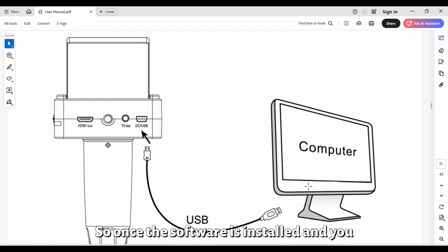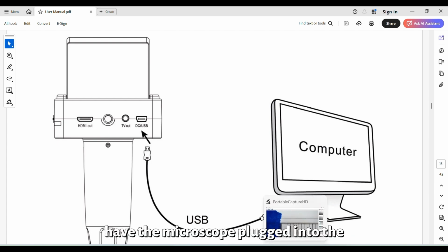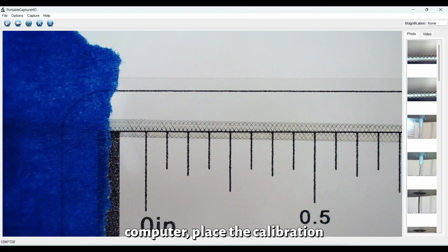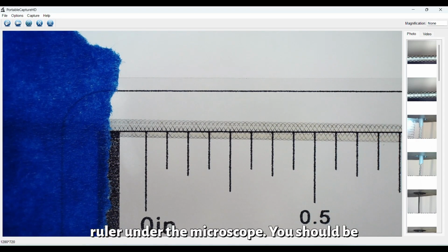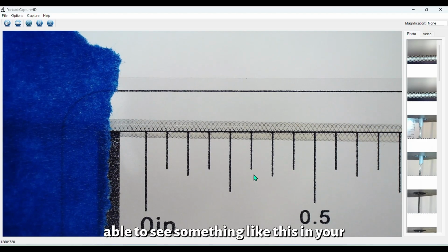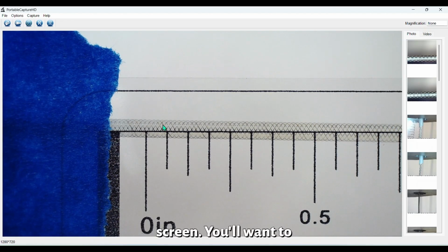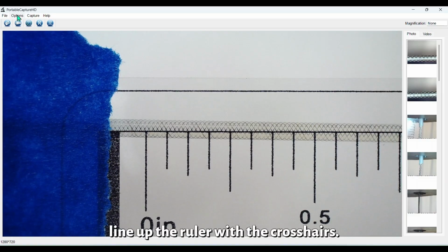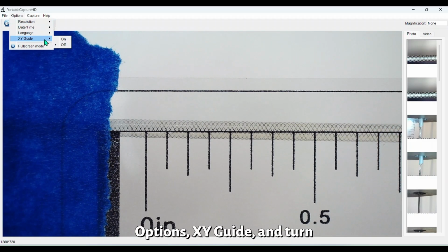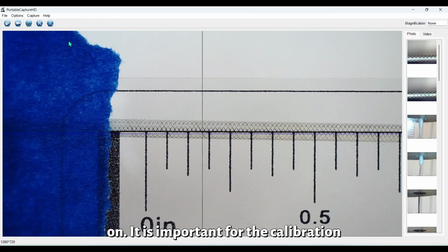So once the software is installed and you have the microscope plugged into the computer, place the calibration ruler under the microscope. You should be able to see something like this on your screen. You'll want to line up the ruler with the crosshairs. To turn on crosshairs, select Options, XY Guide, and Turn On. It is important for the calibration to line up with that.